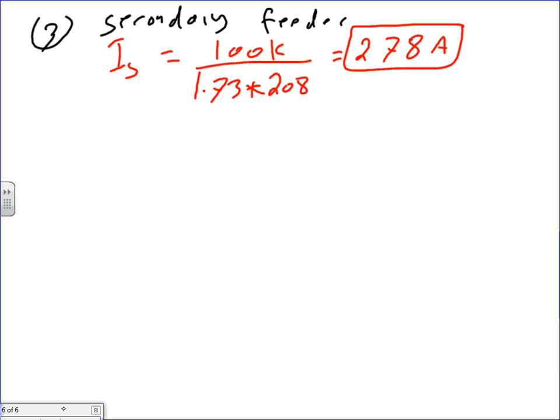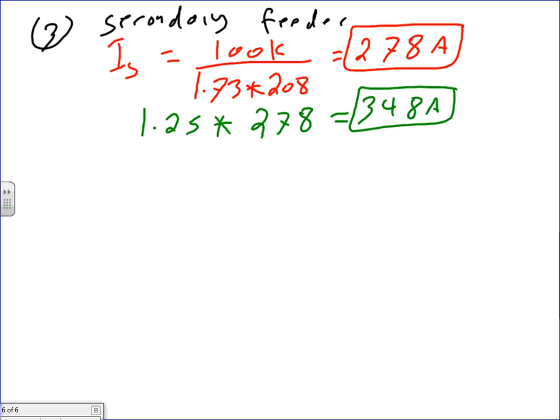Then I need to, again, questionable, some people do 1.25 safety, no problem. But you're going to find later on you don't need to do that code-wise. But we're going to do it 1.25 for the test anyway, times 278. Why? Because we're assuming it's continuous load. And if you do that, you'll end up with 348 amps.